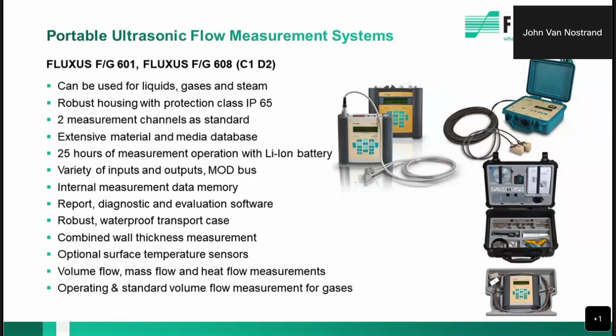The portable meters are excellent too. They're terrific when it comes to doing calibration of other meters like Magmeters in the field. A lot of rural water districts use these; their circuit riders go out and do verification and calibration of Magmeters. And a lot of private companies that do that also use our meters because of the reliability. You've got 2 channels that you can select from, channel A, channel B. So you can do 2 different pipes, or you can do 1 pipe with 2 sets of transducers and average them and even improve that accuracy.